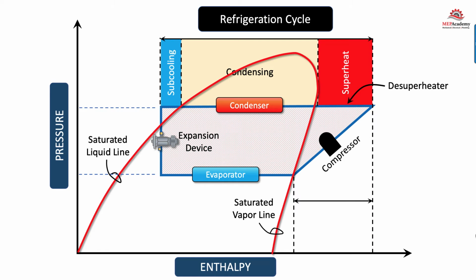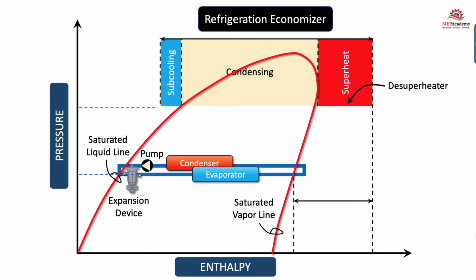For those that love the engineering aspect, here is a look at what the refrigerant chart says the system is doing in economizer mode. As you can see, during the normal refrigerant cycle, the compressor raises the pressure significantly. That doesn't occur during the refrigerant economizer cycle when the compressor is off. Since there is no compressor to raise the pressure, our line flattens out on the vertical pressure line. The compressor is gone and a pump is added to cycle the refrigerant around the system. See our video on how to read refrigerant charts for a better explanation.